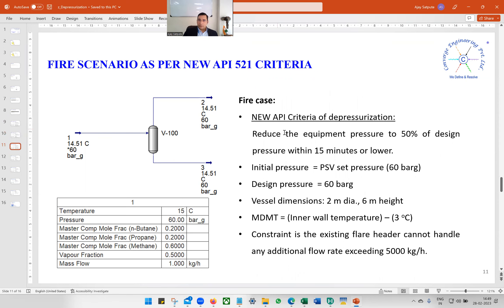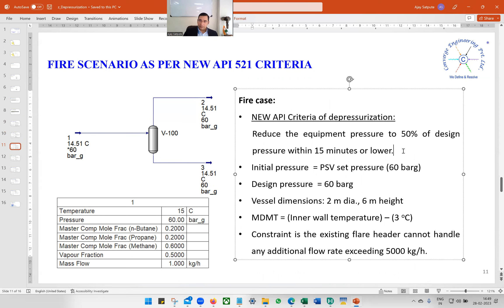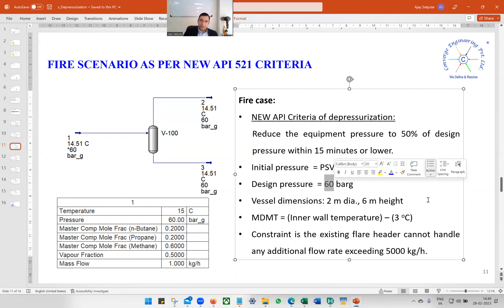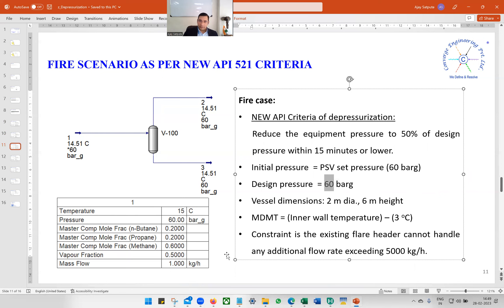Now let us talk about the new API criteria for depressurization. In this case, we don't have to depressurize to 6.9 bar gauge. The final pressure would be 50% of the design pressure — 50% of 60 is 30 bar gauge. So we need to depressurize from 60 bar gauge to 30 bar gauge in 15 minutes.